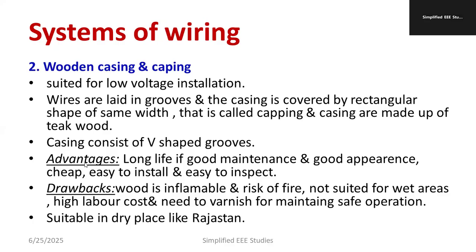The advantages of casing and caping wiring include long life, good appearance, and easy installation and inspection. The major setbacks are that wood is highly inflammable, creating a fire risk; it is not suited for wet areas as the wood gets spoiled; high labor cost is needed for installation; frequent varnishing and maintenance are necessary. It is suitable for dry places such as desert areas like Rajasthan.